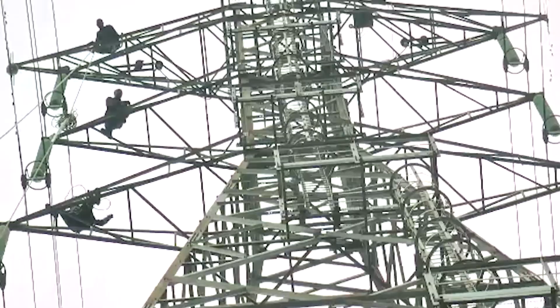These actions are even conducted at times by the live line crew of TCN while the transmission lines have electricity flowing through them. The live line department is saddled with the responsibility of carrying out maintenance on the transmission line while there is still supply on the line, at both the 330 kV and 132 kV voltage levels.